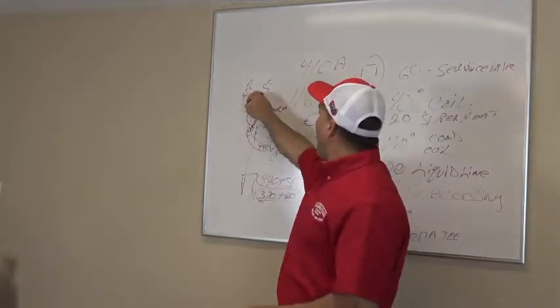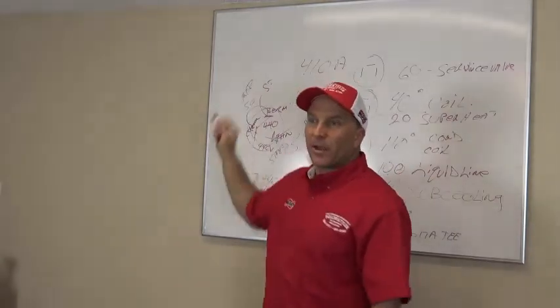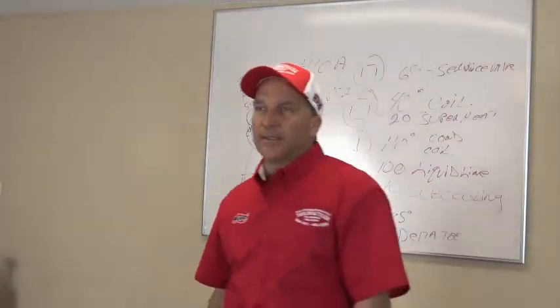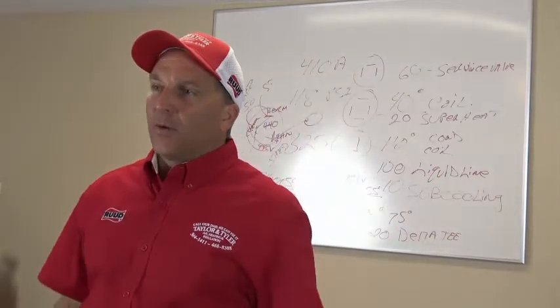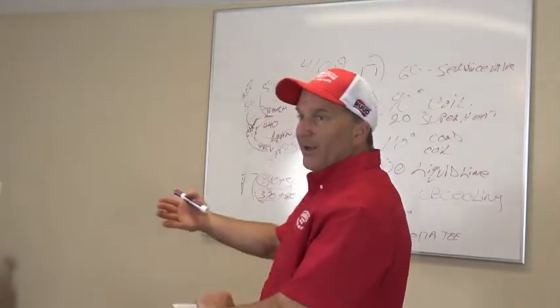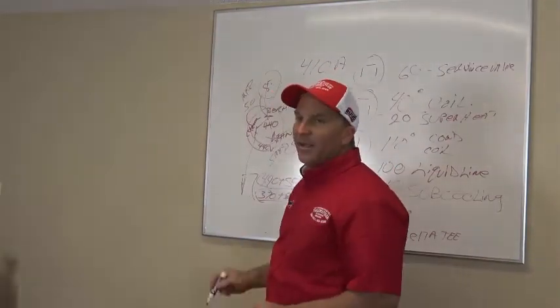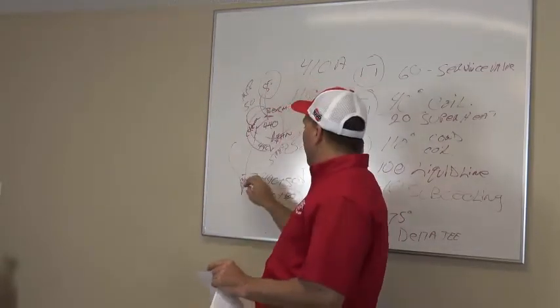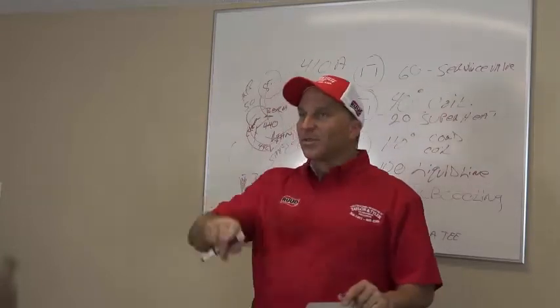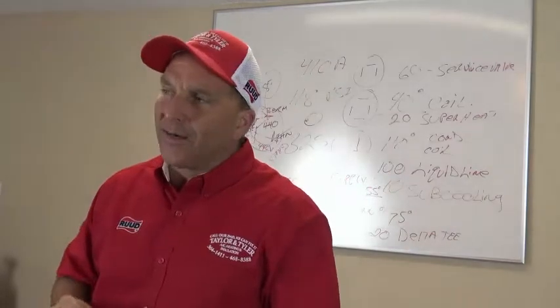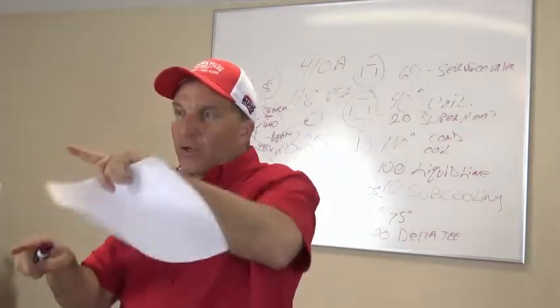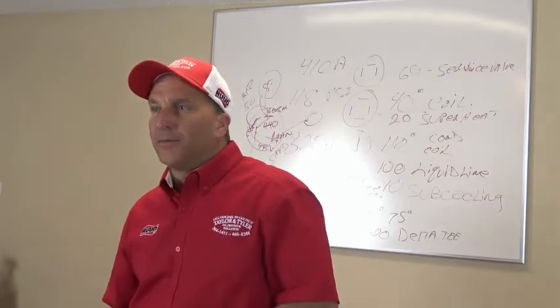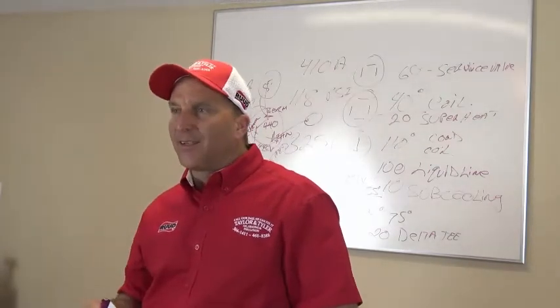All right. If you miswire this thing, and you put your start winding on your common and your hermetic winding over here and that, then you'll short the compressor out. How do you know how the wiring diagram goes? Pick it up, read it, and it's going to tell you purple wire goes to your compressor from start to hermetic. It's going to tell you red wire goes from contactor to the run. Common goes from here to there. It's going to tell you what color wire. So if you ever look at a wiring diagram, not only does it tell you where it goes, but it's going to tell you the color of the wire. So just follow the color of the wire. It's going to tell you exactly where it goes.